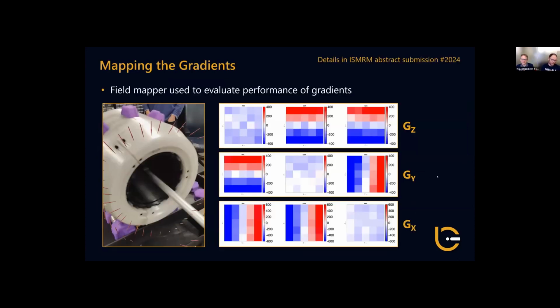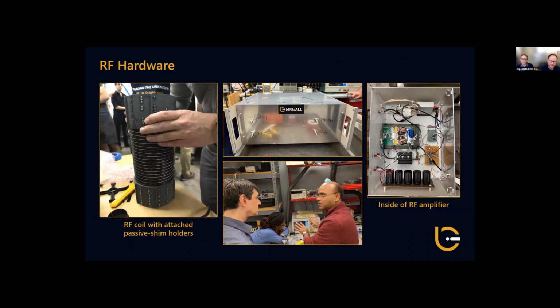Thereafter, we wanted to be able to map the fields generated by the gradients. So we inserted the gradients into the form or the holder, and we drove them with 1 amp, and we measured the field across the 3 different axes. And here we can see this scan over a field of view of about 10 centimeters, I believe. Similarly, in terms of RF hardware, the transmit receive solenoid was squeezed between the 2 passive shims. In addition to that, we designed an RF amplifier with various custom components.